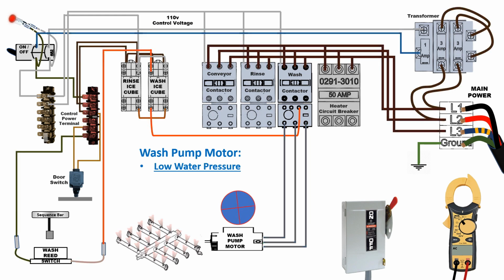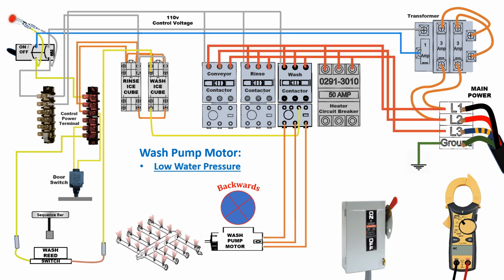Second, and the most common, is that the motor could be running backwards. Motors running backwards is caused by the polarity being reversed on a three-phase line. This can be done when rewiring new pumps onto the system, not putting the wirings back in the direct contact that it was, or it can be from electrical work being done within the customer's facility and the electricians have reversed the polarity of the three-phase lines. Either case, this is an easy fix.